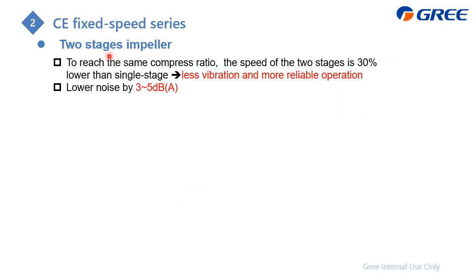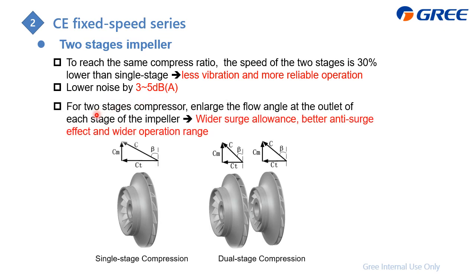What's the benefit of the two-stage impeller? First, to achieve the same compression ratio, the speed of the two-stage is about 30% lower than single stage, and lower speed leads to less vibration and higher reliability during operation, right? On the other hand, lower speed also means lower noise, and we can lower it by about 3 to 5 decibel A. And also for the two-stage compressor, we can enlarge the flow angle at the outlet of each stage of the impeller, which can widen the surge allowance, which is better for the anti-surge effect and a wider operation range.